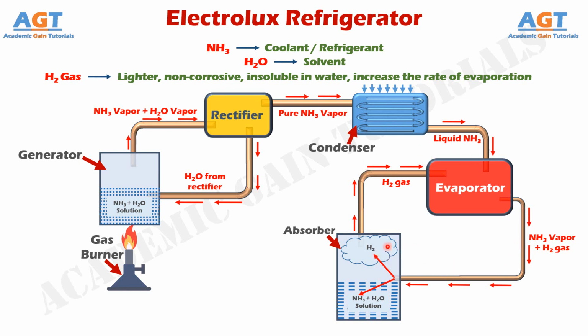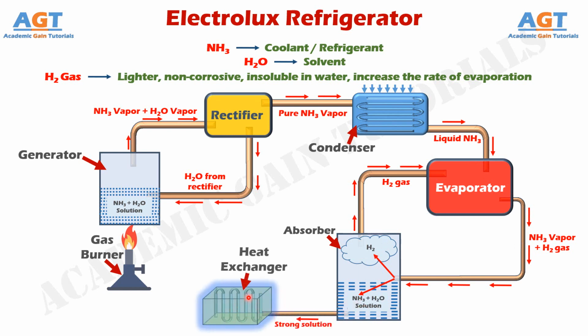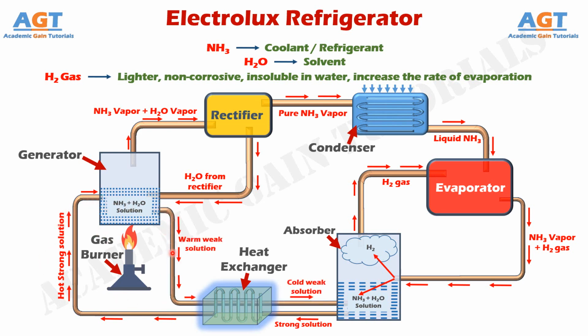After that, connected to this absorber we have a heat exchanger over here. As we know, the heat exchanger is used to exchange heat from the hot body to the cold body, and from the cold body to the hot body. So, this strong ammonia-water solution from the absorber will now enter the generator after passing through this heat exchanger. Now, this strong solution needs to be hot before going into the generator.